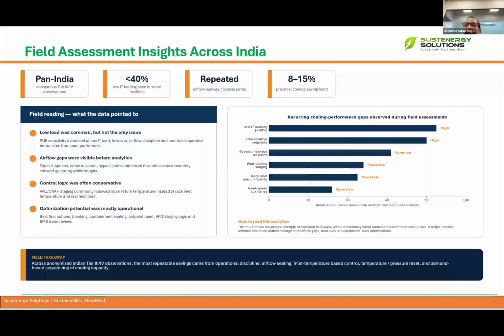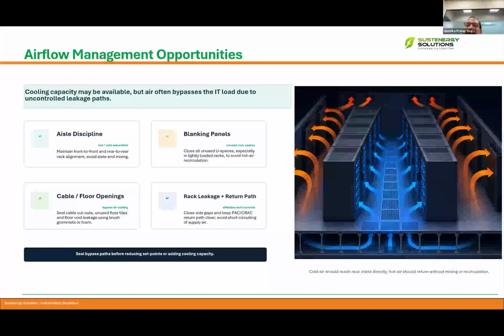If you see the right-hand side graph of recurring cooling performance gaps, most of the time we see low IT loading and conservative set points. These are the most commonly found problems. Then bypass leakage is also a common problem. Sometimes we find poor cooling staging, rack inlet non-uniformity, or fixed-speed auxiliaries. Some of the sites don't have control automation or drives installed to control their fans. That is also one problem, and we can take care of it with better automation these days.